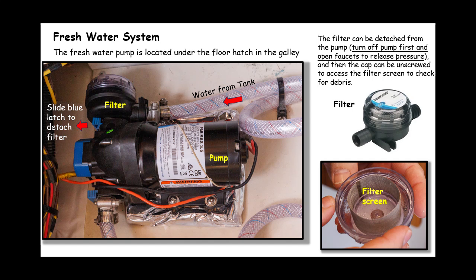One of the maintenance items would be to check the filter for debris, and in order to do that, turn off the power to the pump, open some of the faucets to release pressure from the system, and then this little blue tab can be slid, and that'll allow you to pull the filter housing off, and then the cap itself can be unscrewed, and then the screen can be lifted out and inspected.